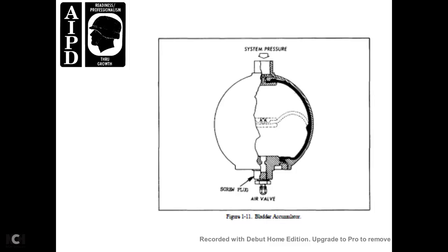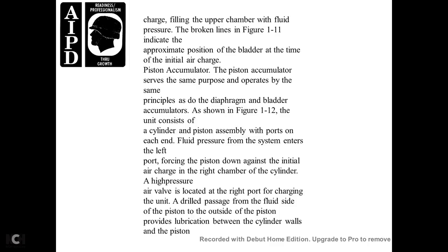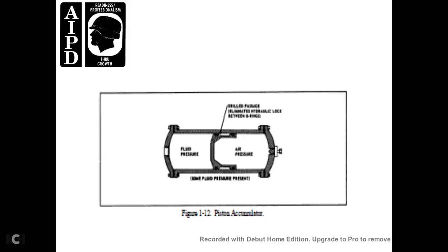Piston Accumulator. The piston accumulator serves the same purpose and operates on the same principle as the diaphragm and bladder accumulators. As shown in figure 1-12, the unit consists of a cylinder and piston assembly with ports on each end. Fluid pressure from the system enters the left port, forcing the piston against the initial air charge in the right chamber of the cylinder. A high-pressure air valve is located at the right port for charging the unit. A drilled passage on the fluid side of the piston provides lubrication between the cylinder walls and the piston.